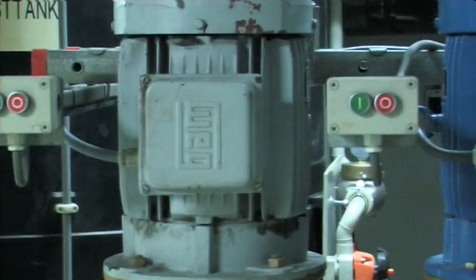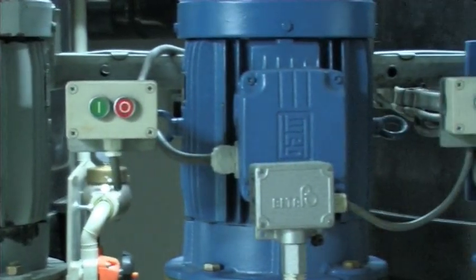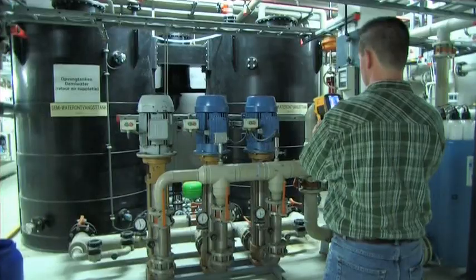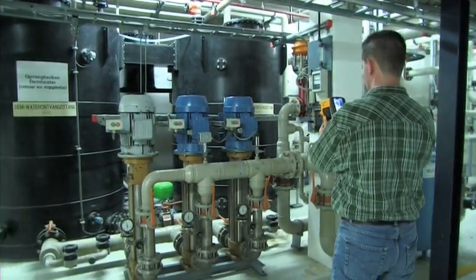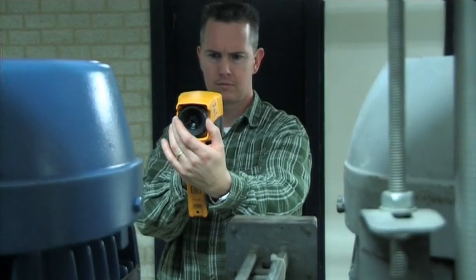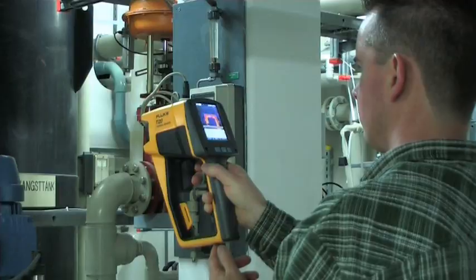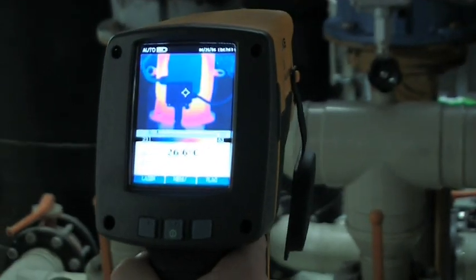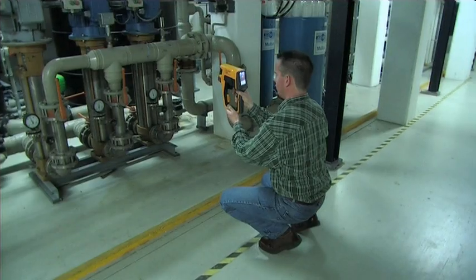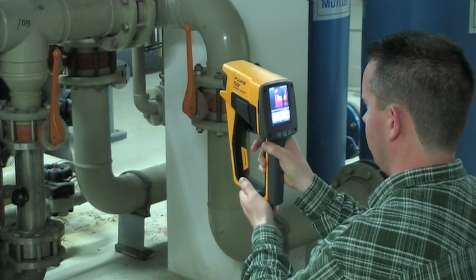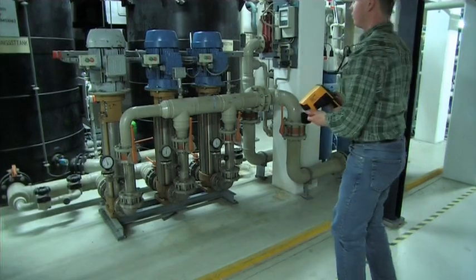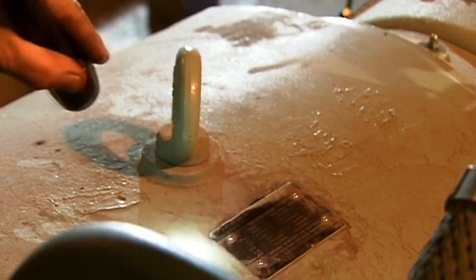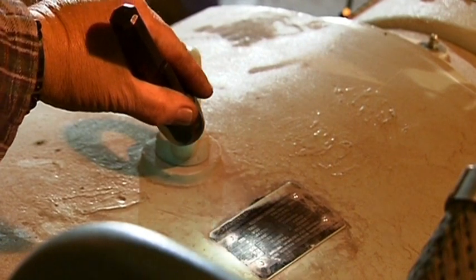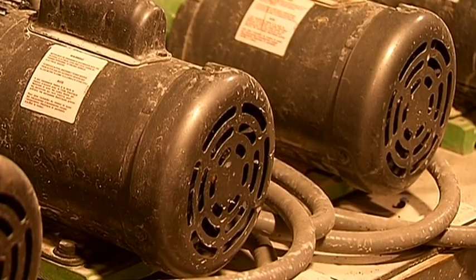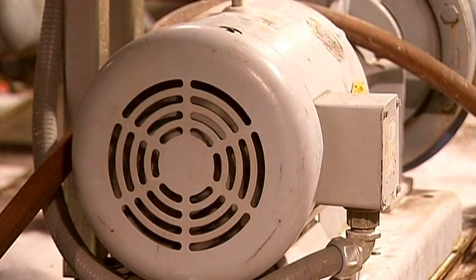When checking electric motors, do so under normal operating conditions. Unlike an infrared thermometer that only captures temperatures at a single point, a thermal imager captures temperatures at thousands of points in real time. A single image includes all critical components, such as the motor, shaft coupling, motor and shaft bearings, and the gearbox. All motors should list the normal operating temperature on the nameplate. Even though a thermal imager cannot see the inside of the motor, the outside temperature is a good indicator of what's happening inside.